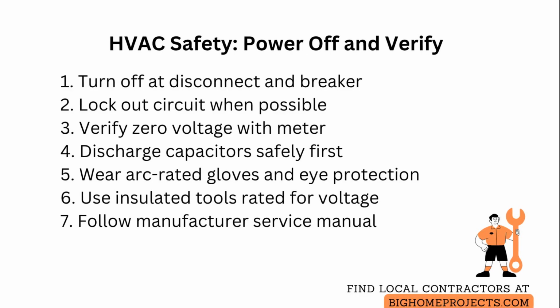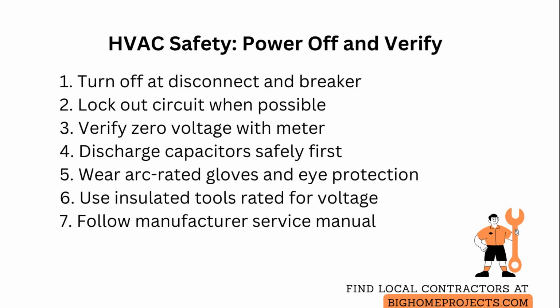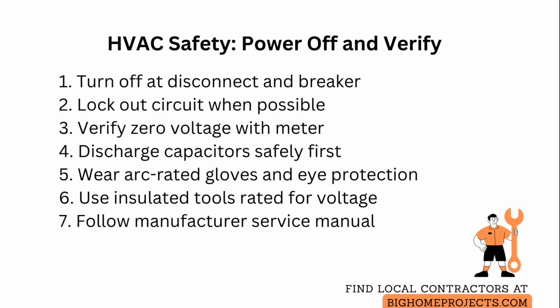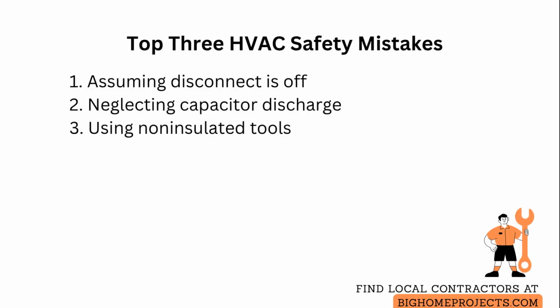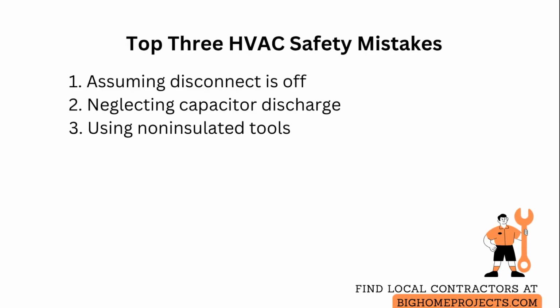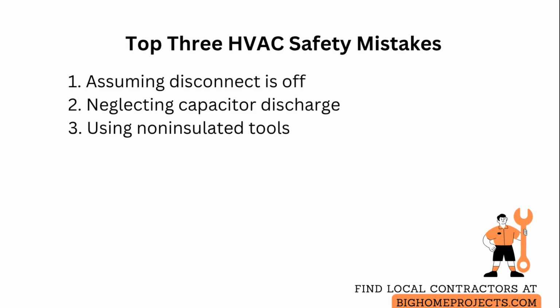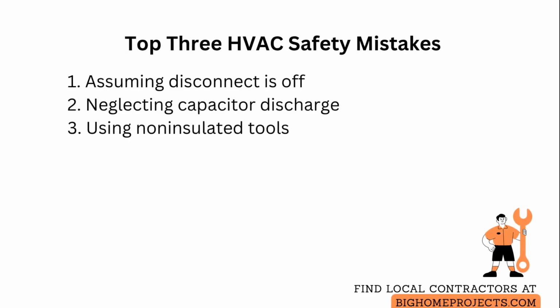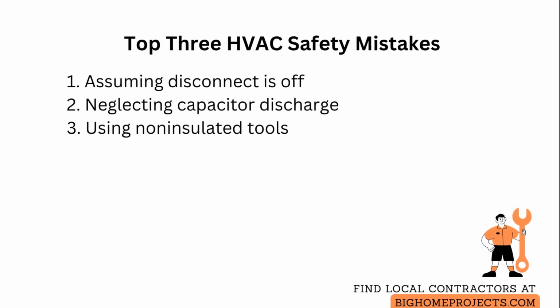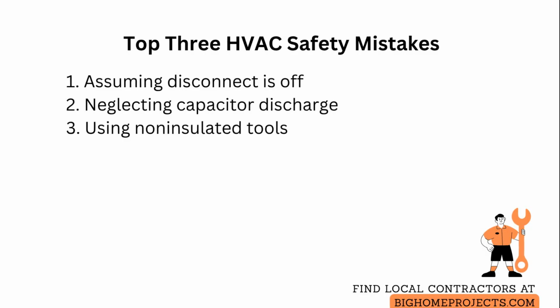Follow the manufacturer service manual for component-specific procedures and torque values, and document any wiring changes with clear labeling and photos for reassembly. Common mistakes are assuming the disconnect is off without testing, which can be avoided by always verifying zero voltage with a meter and applying lockout tagout procedures to prevent others from restoring power.